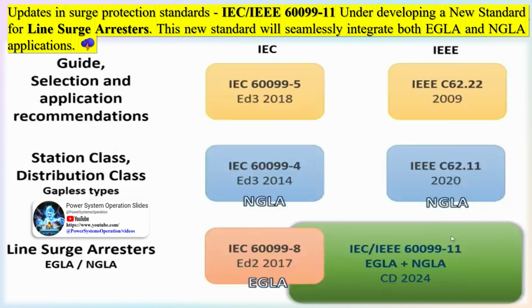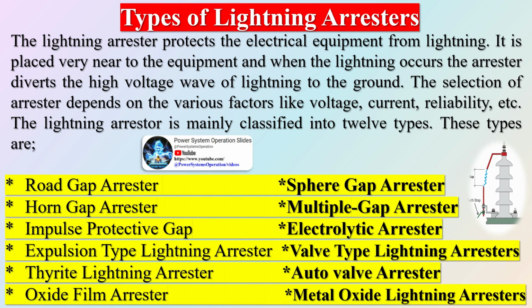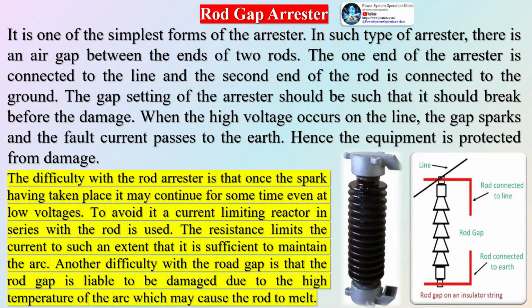Surge arresters are used in substations to protect transformers, circuit breakers, and other critical equipment from overvoltage transients caused by lightning strikes, switching surges, or other events. Distribution lines. Surge arresters are installed on distribution lines to protect pole-top transformers, switchgear, and other equipment from overvoltage transients caused by lightning strikes or switching operations. Industrial facilities. Surge arresters are used in industrial facilities to protect sensitive electronic equipment from overvoltage transients caused by lightning strikes or power surges. Residential and commercial buildings.